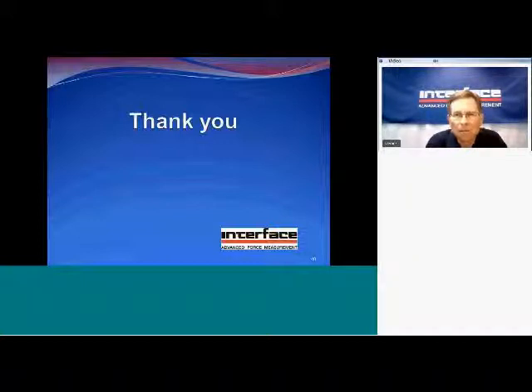So, for example, we send our load cell standard to NIST to be deadweight calibrated. The deadweights at NIST had to be concerned about local gravity so that they exert the correct amount of force. However, the load cell that is now calibrated in units of force no longer cares about gravity. That load cell can be used at any location on any planet. It only responds to force. It doesn't care about gravity. That's a nice thing about the comparison method of calibration.